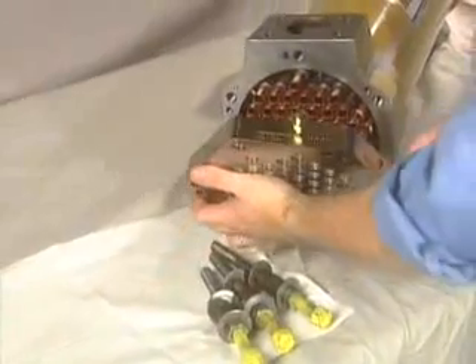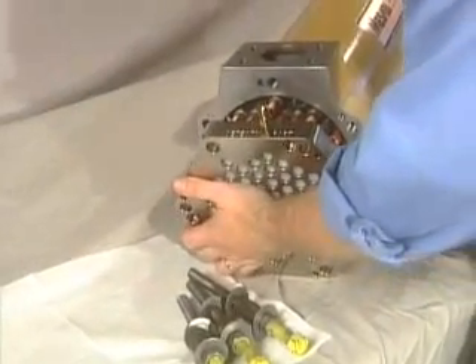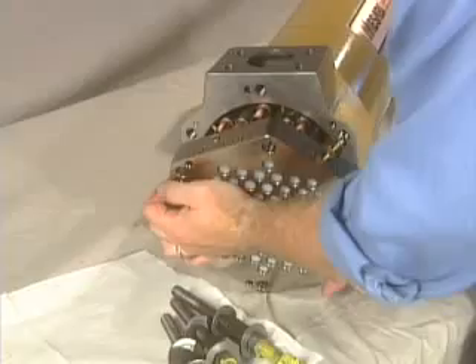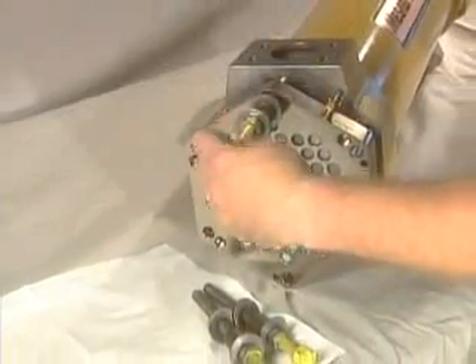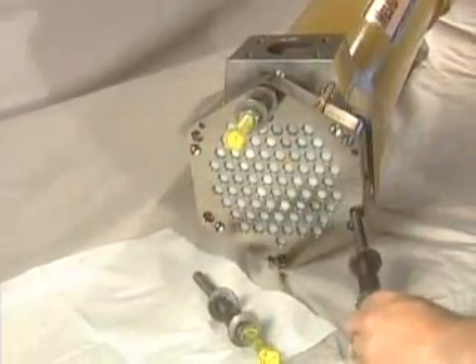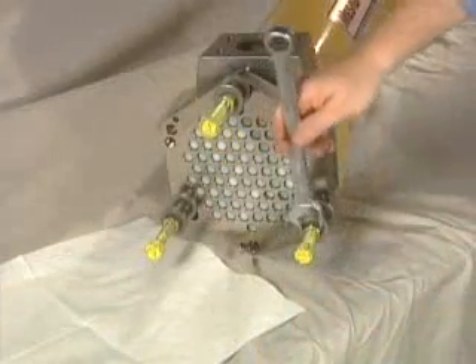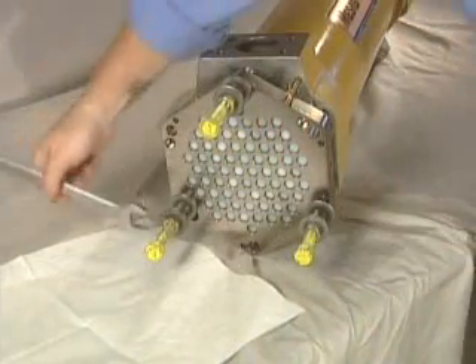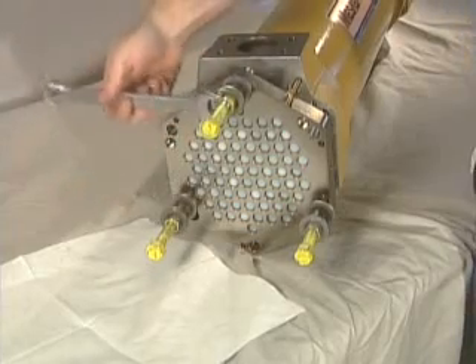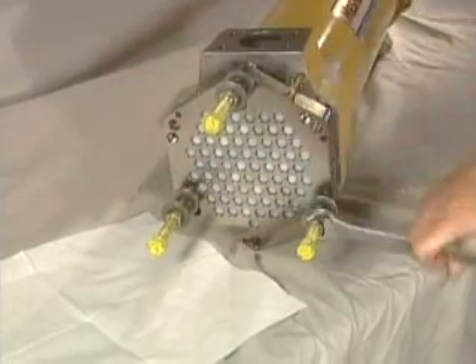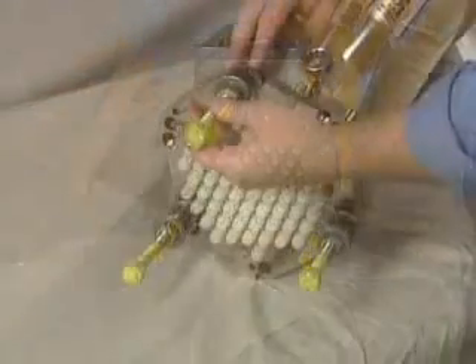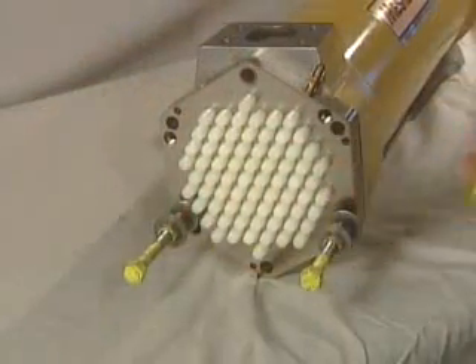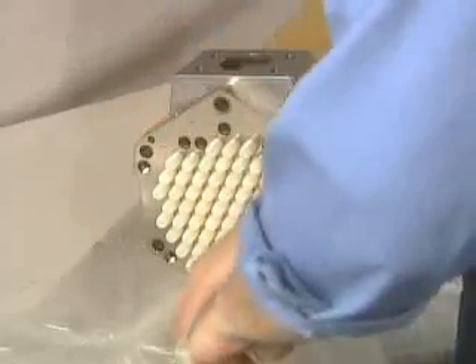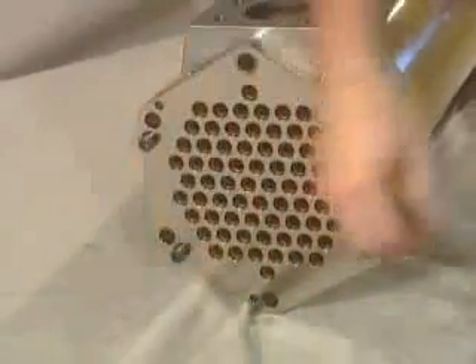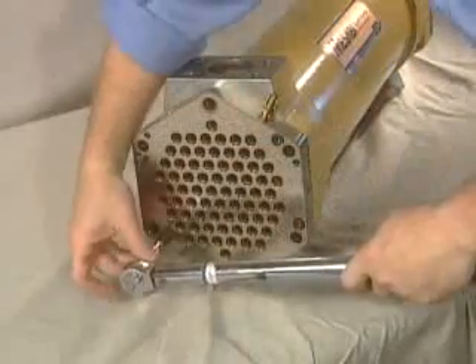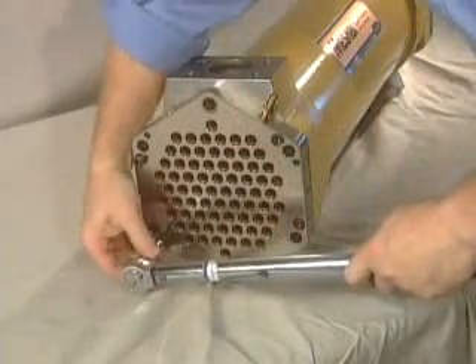Align the second header plate holes with the tubes and its alignment pins with the alignment holes of the shell flange. Pull the header plate in place with the header plate drawdown bolts. Do this uniformly by alternately tightening each bolt around the perimeter 1/2 turn at a time. Tighten until the header is tight to the shell. Remove the header plate drawdown bolts. Remove plastic assembly bullets. Install proper header retainer bolts and torque as recommended in the System Protector Service Manual.